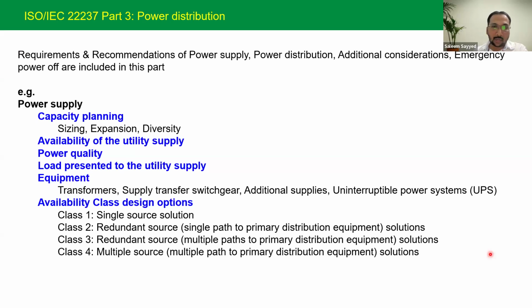If you see their comparison of the electrical and cooling distribution, they are almost the same. I have not come across a case where they talk very differently from each other. This is a major point where the designer has to struggle: which standard to follow, Uptime, TIA, or IEC. Okay, that is point number one.